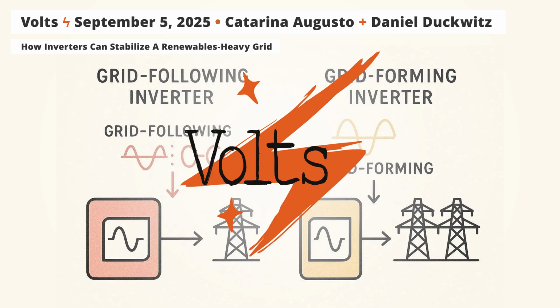So with voltage control services, it's once again similar - you have an instant imbalance that needs to be balanced, requiring some inherent reaction or a very fast control scheme. Then there is more the steady state balancing of the grid, to readjust voltages closer to nominal within about 5 minutes after some event. This is similar to frequency and active power balancing, but it's usually treated as a separate category. There's voltage stability and frequency stability - in some big real-world events they can interact, but in theory, in the textbook, they are separated.